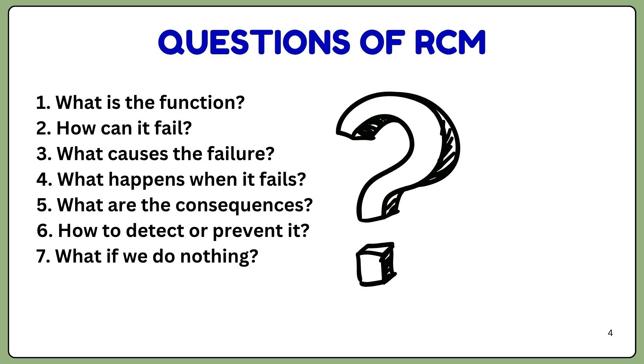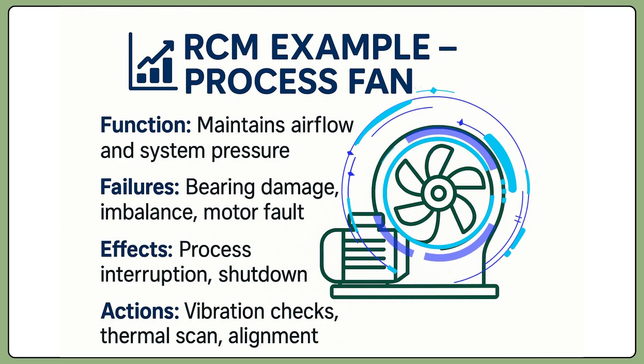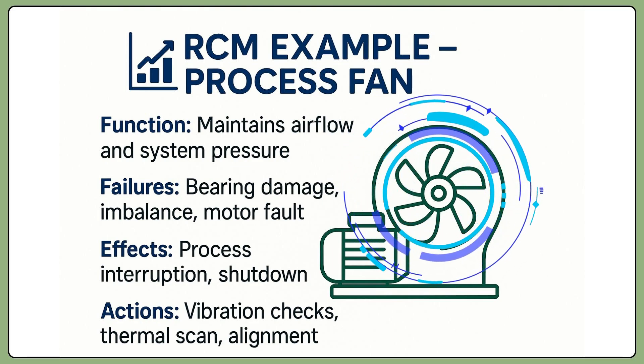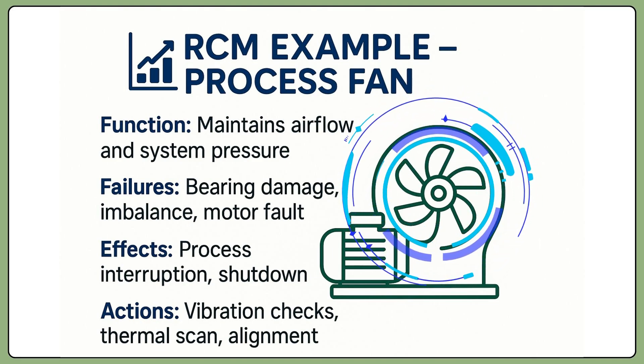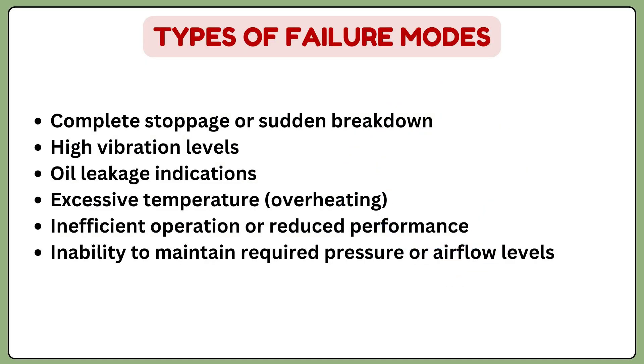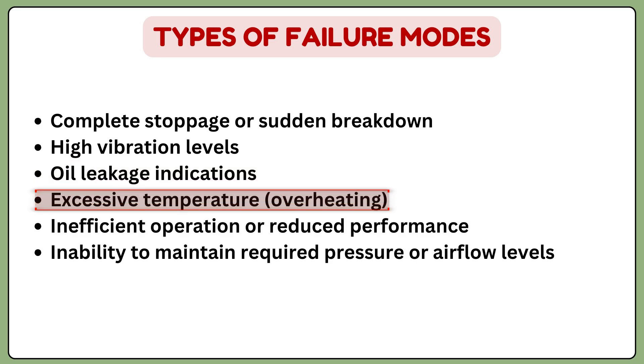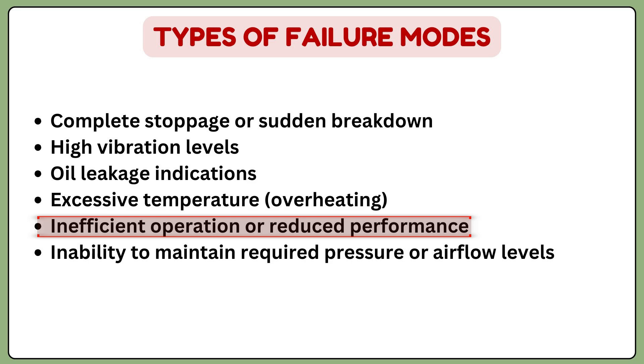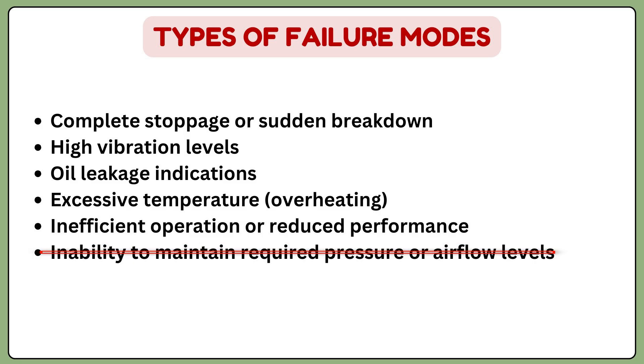Let's go through a real example using a process fan. Starting with the first question — the function: the process fan supplies hot gases from one part of equipment to another. For the second question — failure modes — either the fan will completely stop or go to breakdown, it will start to vibrate, there may be oil leakage, high temperature, or the fan will run inefficiently with pressure or flow not meeting the required benchmark.